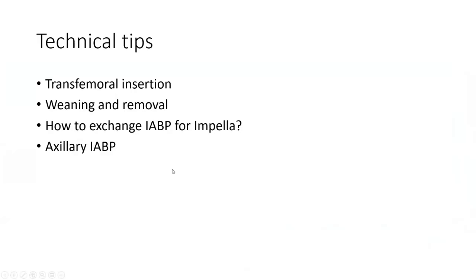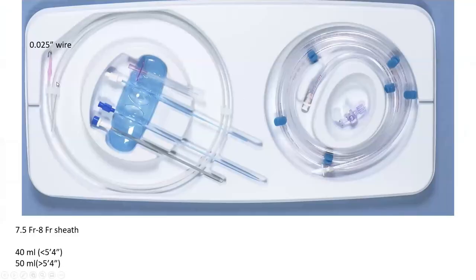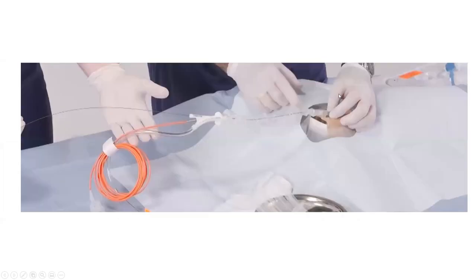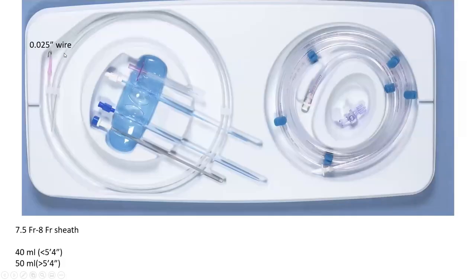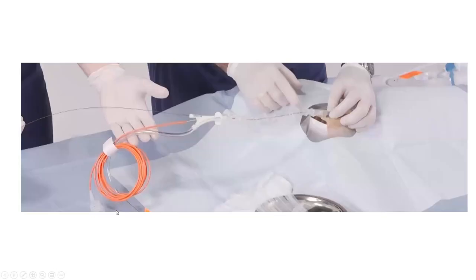So do not dip it in water, okay? So what you do, you advance it without having been touched with fluid and with dry hands, you advance it using 1 inch. You put your finger 1 inch behind, and you push with 1 inch steps until you get it through. If you're having a hard time advancing it, one, you can suck on the helium gas lumen again with a syringe, suck negative again. Two, you can use a stiffer wire. The wire that comes with that console is very flimsy. You can use a 0.025-inch Amplatz wire, it's available, or you can use a 0.018-inch V18 stiff wire, okay?